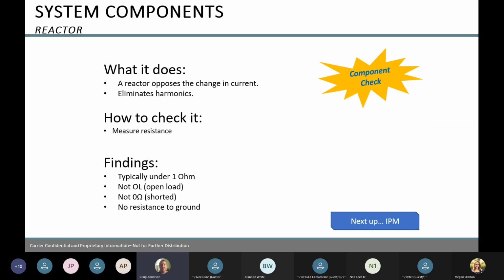On a reactor, we're usually at a little under 1 ohm. If we're any higher or you're at 0, then we're looking at some issues. We're not looking for an OL, that would be an open load. We're not looking for that. And then no resistance to ground. So we're just checking the resistance to that. It should be around 1 ohm.